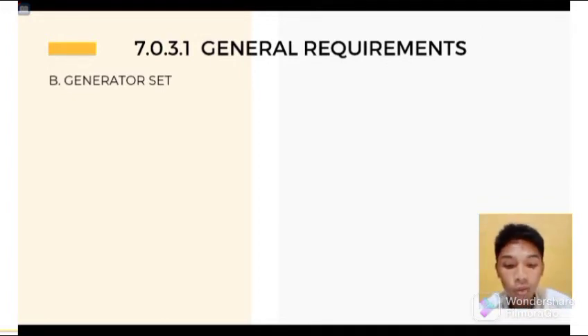Okay, for number 2, internal combustion as prime movers. Where internal combustion engines are used as the prime mover, an on-site fuel supply shall be provided, with an on-premise fuel supply sufficient for not less than 2 hours full demand operation of the system, where the power is needed for the operation of the fuel transfer pumps to deliver fuel to a generator set day tank. This pump shall be connected to the emergency power system.